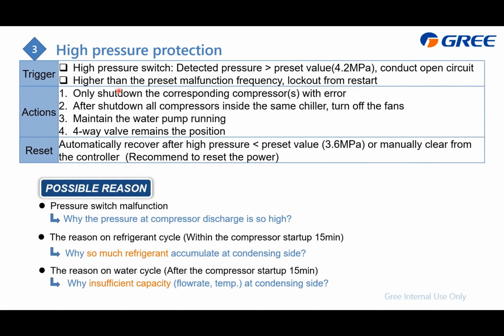Next type is the high pressure protection, and this comes from the high pressure switch, which means the detected pressure is higher than the preset value, about 4.2 megapascal. We will cause the switch to open circuit. Then when the system receives this signal, we will do the following actions. First is to shut down the compressor, and if all the compressors inside the same chiller are turned off, we will turn off the fans in this chiller.